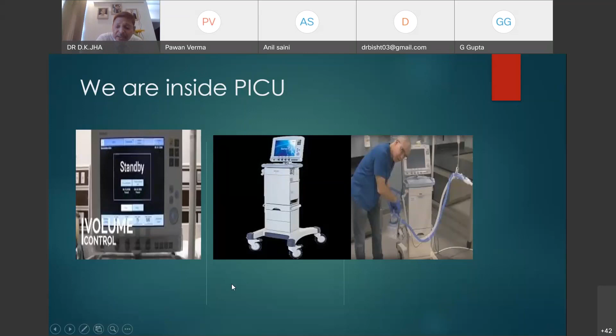If there is an inbuilt compressor in the ventilator, there is no need of that. There is the inspiratory and expiratory limb of this tubing, there is an expiratory chamber, and there is a humidifier. All you have to do is set it up. If you are working in ICU and there is a call from the ward, do all this work, make the power on and keep the ventilator on standby mode. As soon as the patient enters your ICU, just start ventilation without delay.